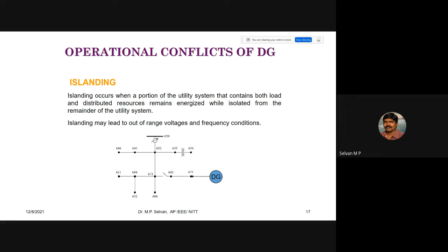And now we are moving into another concept, from DG to microgrid. Normal DG to microgrid. What I stressed in the previous discussion is that when I say DG, distributed generator, we are following the grid. If the grid is not there, the DG also will not work. But there is no use, right? I want to utilize the renewable energy most of the time, whenever it is available. I can install a 2 megawatt solar power plant and connect to an 11 kilovolt distribution network. But if the distribution network fails, that particular feeder is taken out of service, or if there is a low voltage, the inverter also will stop its operation.